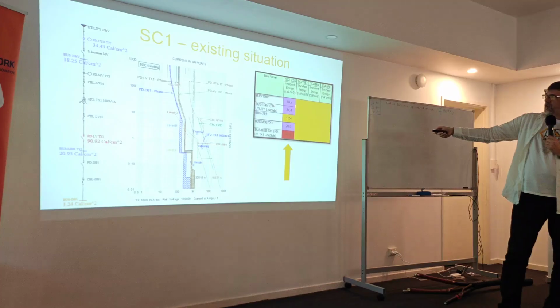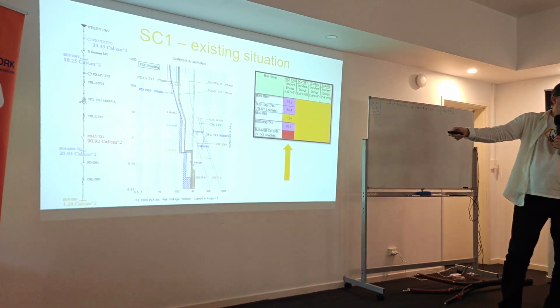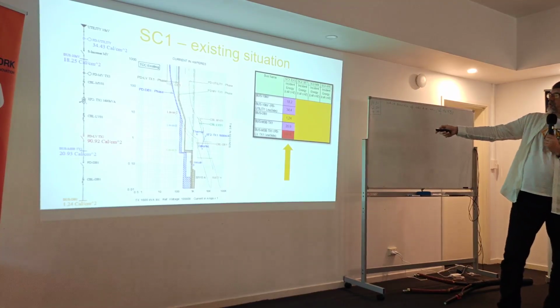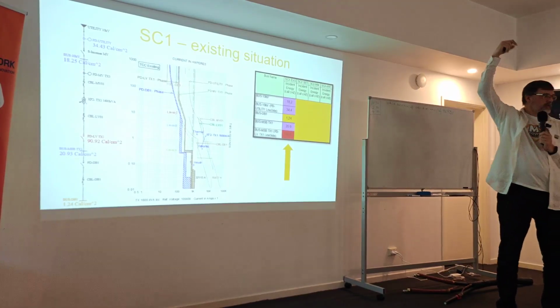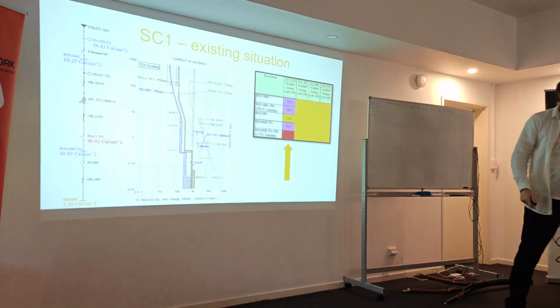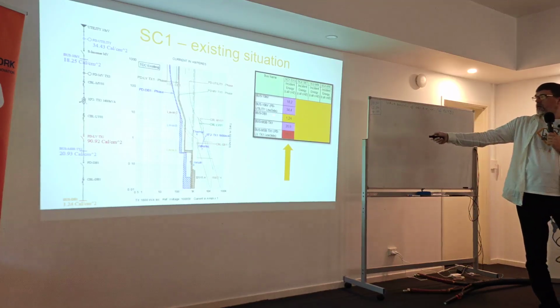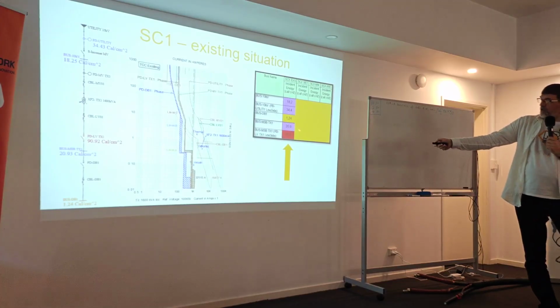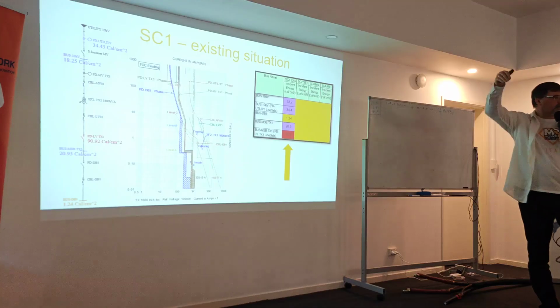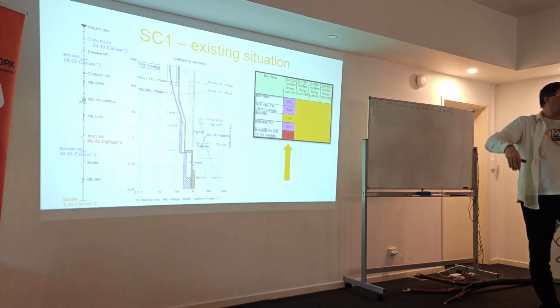And we have a 10 kV station, we have 18.2 calories, which is on the bus level. On the breaker itself it is 34 calories, because there is no protection from the top modeled, yeah? So it will stay like this. On the low voltage one, we have 20 calories on the bus, but 90 calories on the incoming panel, yeah? So if you have an incoming panel from the transformer, it's 90 calories.